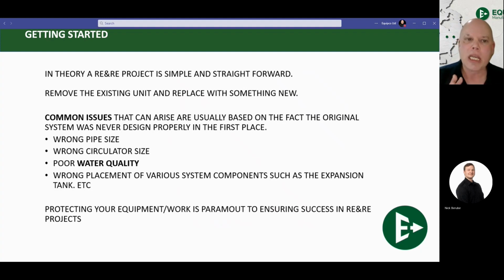That's a good place to check to make sure that you're not going to have that common issue come up. Another one that we come across is the wrong circulator size. We deal with circulators all day, every day. Hydronic systems are designed to have the right flow going at the right speed to the right emitter. Wrong size circulators can either give us underpumping or overpumping situations where we're sending too much heat to an area or not enough heat to an area. Wrong circulator sizes can be quite an issue with delivering the heat that is required.